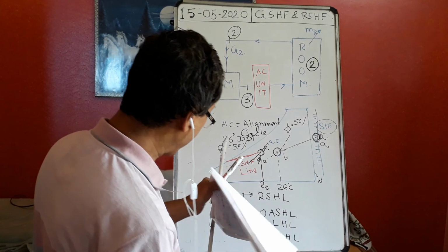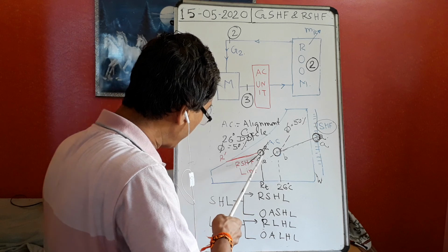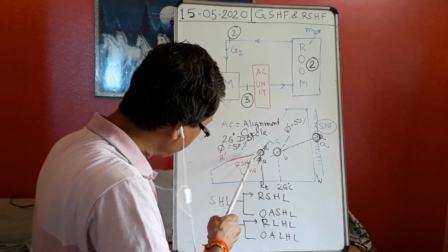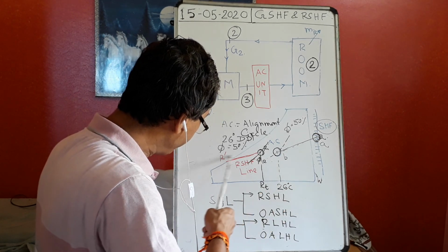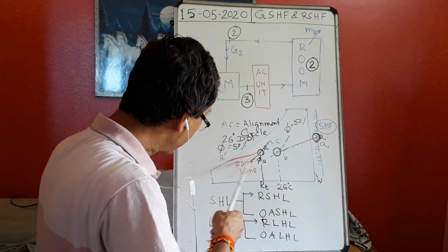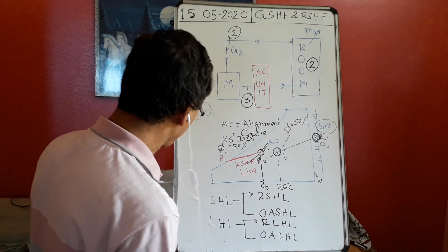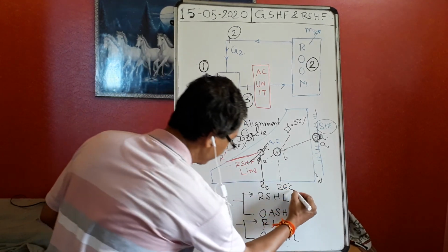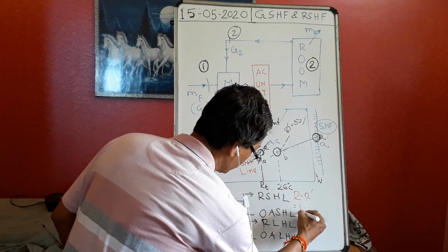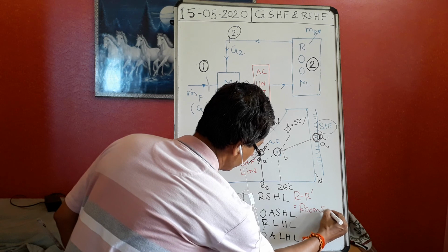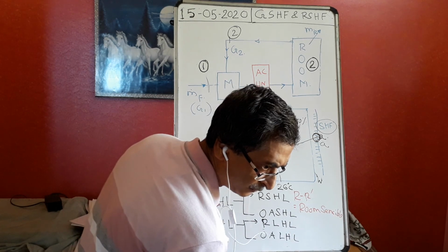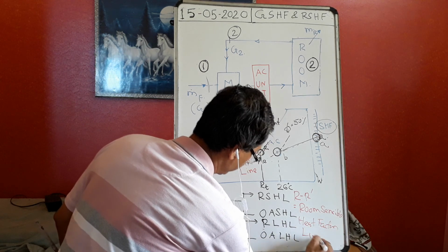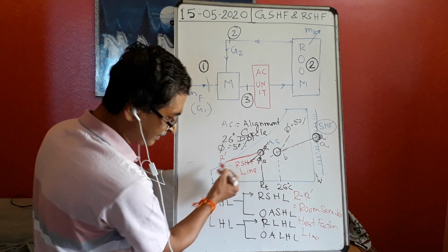Now here come to this diagram again. So the room condition R. Now if I draw one red line parallel to AB, then this line is called RR dash. This is called the room sensible heat factor line, simply the RSHF line. So this line is the RSHF line.